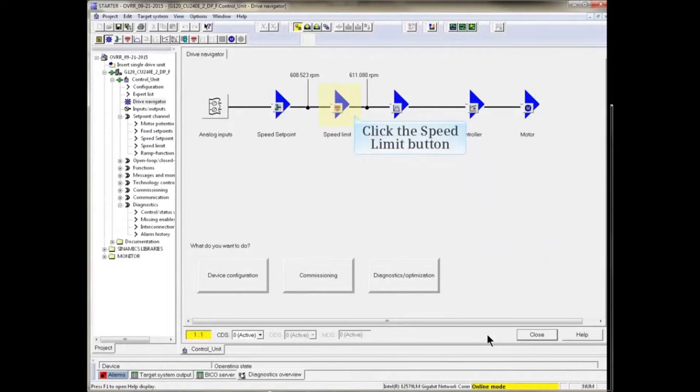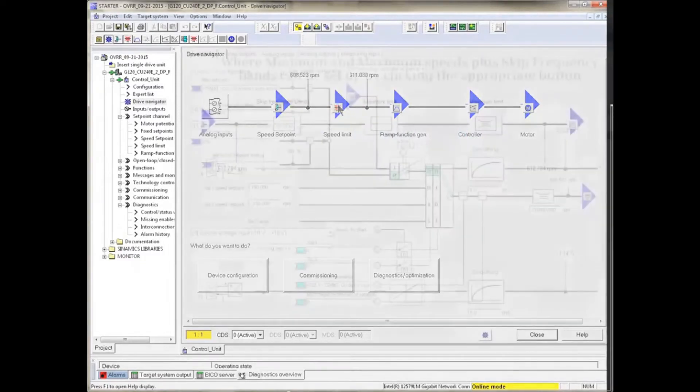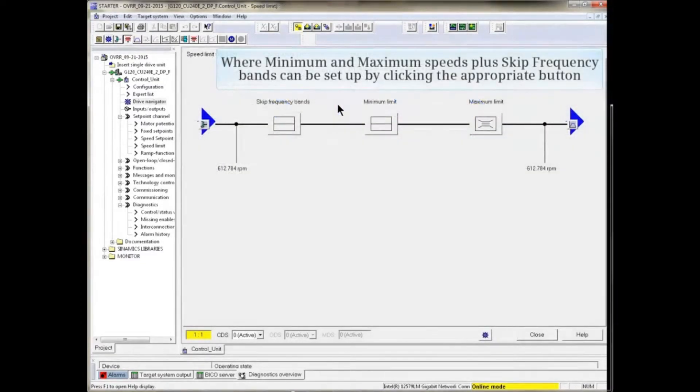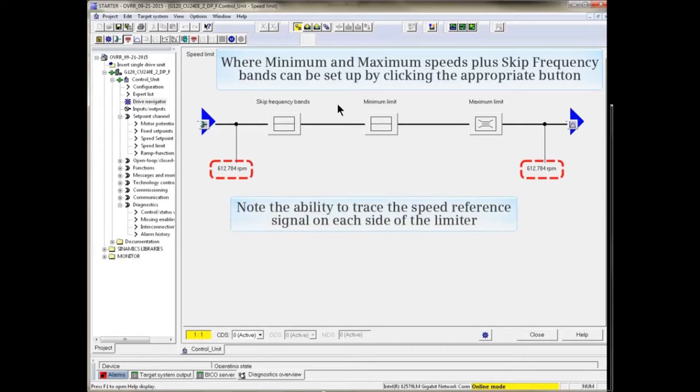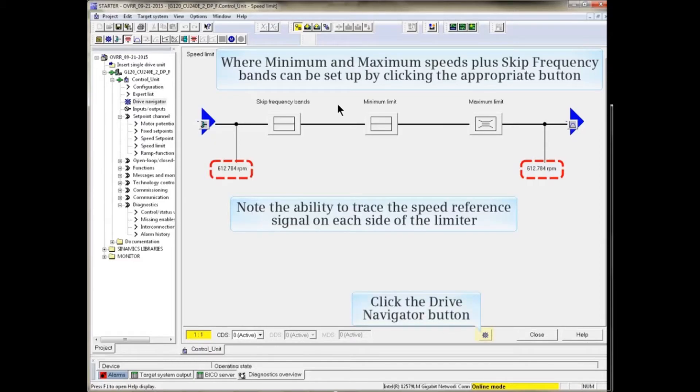Navigating back to Drive Navigator, we can now look at the Speed Limit window, where minimum and maximum speeds plus skip frequency bands can be set up by clicking the appropriate button. Note the ability to trace the speed reference signal on each side of the limiters.